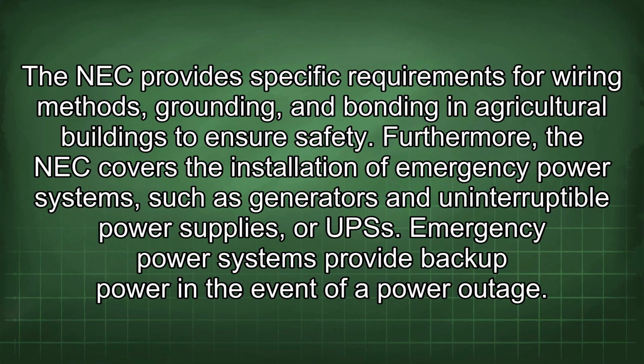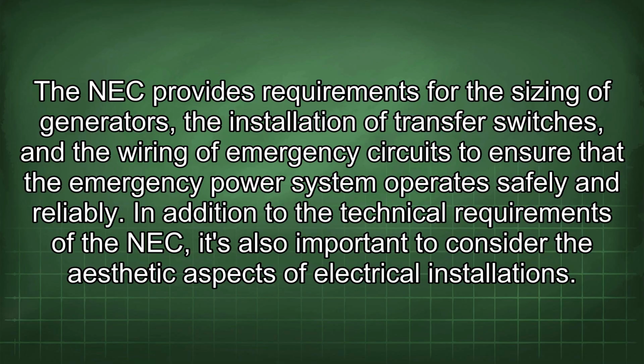Furthermore, the NEC covers the installation of emergency power systems such as generators and uninterruptible power supplies, or UPSs. Emergency power systems provide backup power in the event of a power outage. The NEC provides requirements for the sizing of generators, the installation of transfer switches, and the wiring of emergency circuits to ensure that the emergency power system operates safely and reliably.